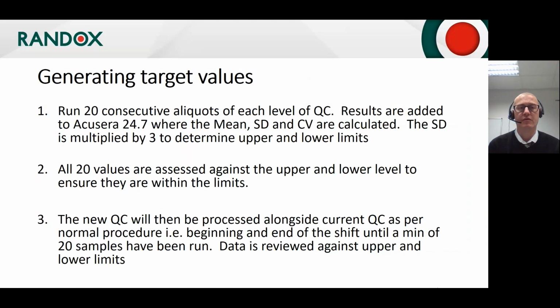So initially we run 20 consecutive aliquots for each level of QC. These results are added to Acusera 24/7, where the mean, SD and CV are calculated. This SD is then entered into the intra-precision field on 24/7. This value represents the random error of the system. We also keep an initial recording of these values as a hard copy. The SD is multiplied by 3 to determine upper and lower limits for each particular assay.